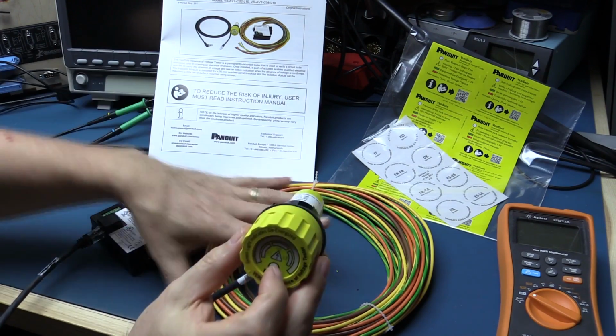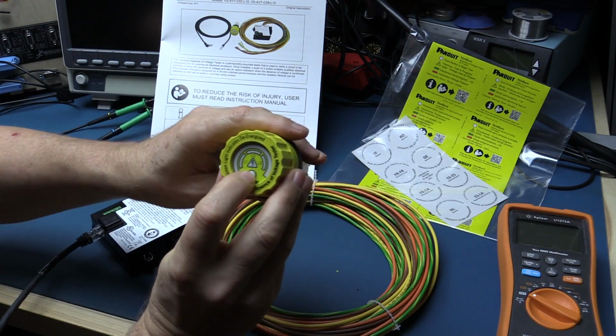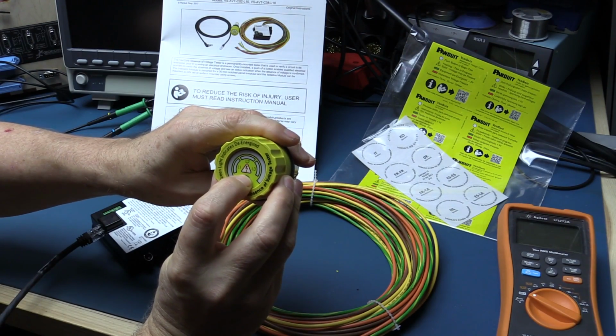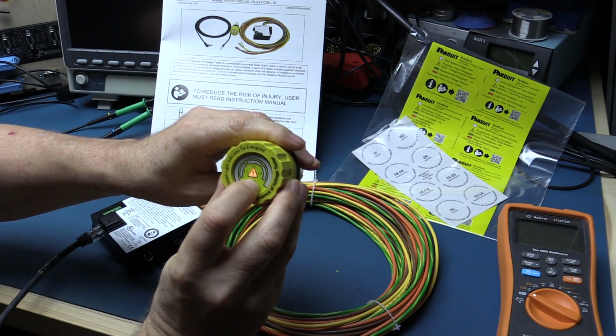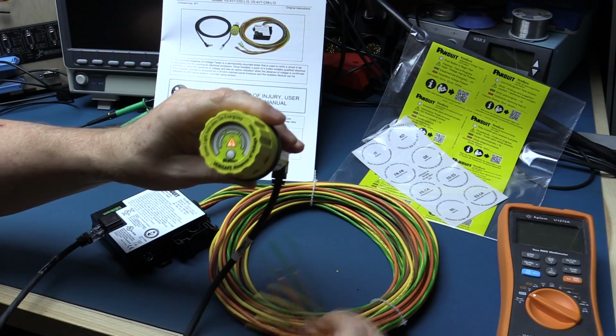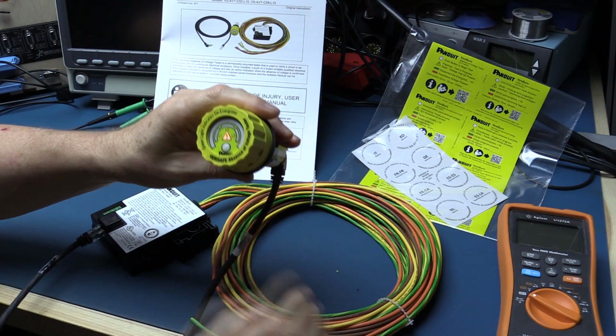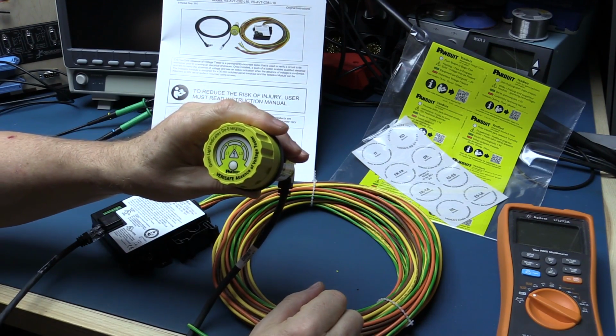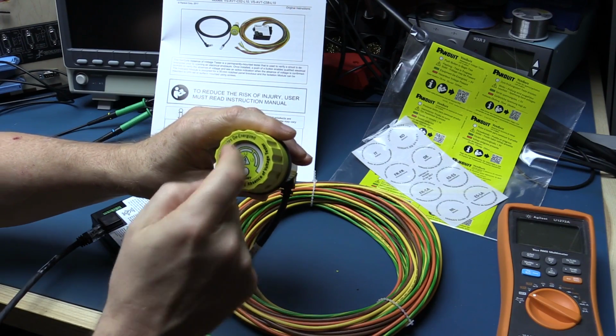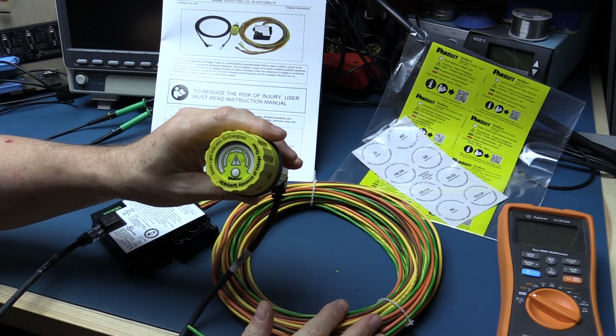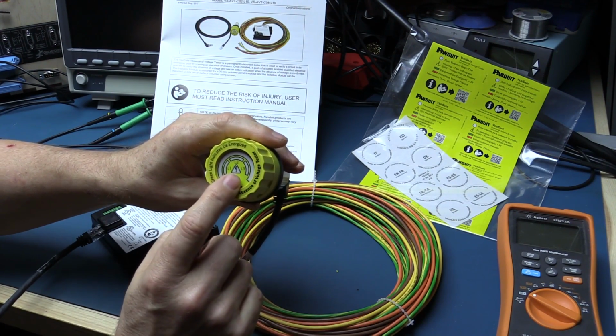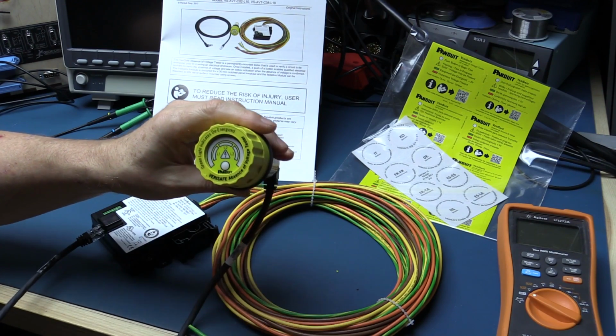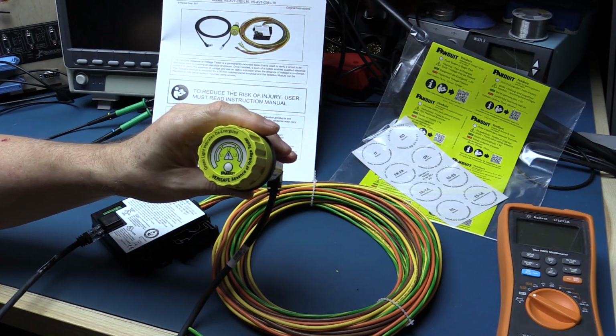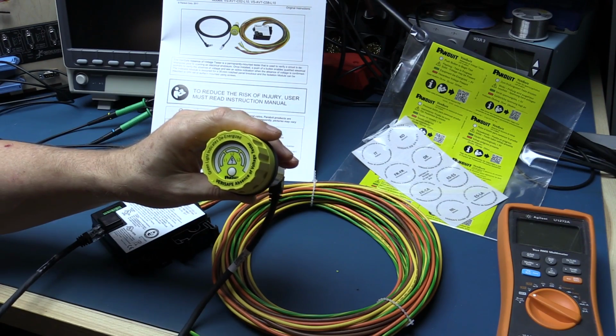So if I have nothing connected on these cables and I just simply push this, because it can't sense what's going on - since none of the cable ends are connected - it's warning me that there could be volts present. There's no red lights to say that there is volts, but there's no green ones to say that there isn't either. So it's warning me that this thing has detected that it's not wired up properly.